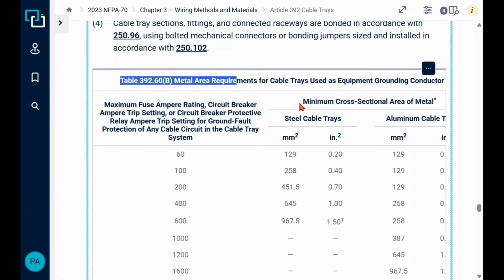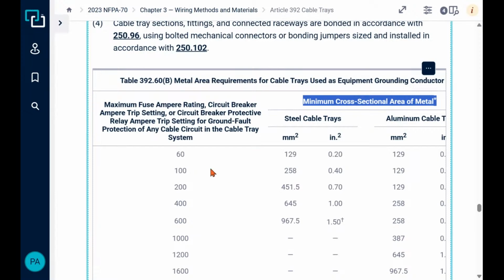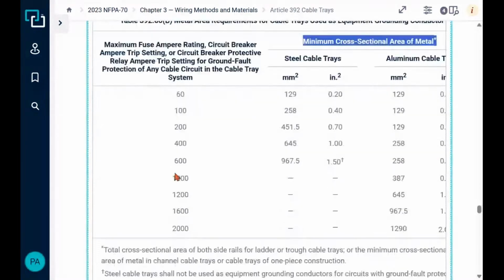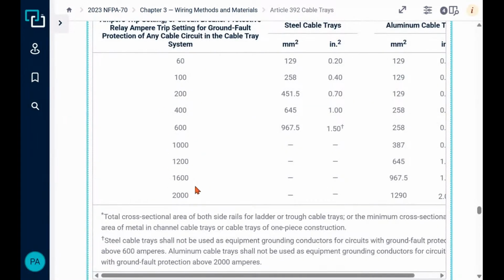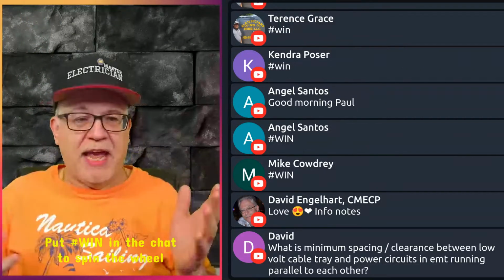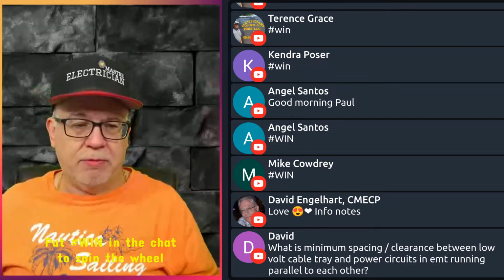This is telling you the minimum cross-sectional area, right? Based on the amp rating, okay? So it's essentially like we do for an overcurrent protective device to size a wire type equipment ground. You notice we don't do this for raceways, right? EMT doesn't have this little table, but we do for cable trays, okay?